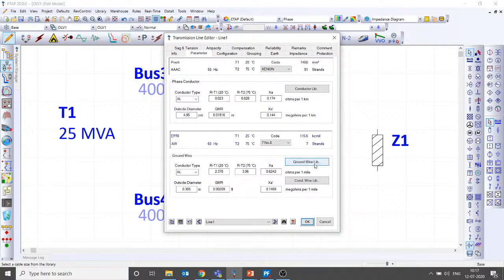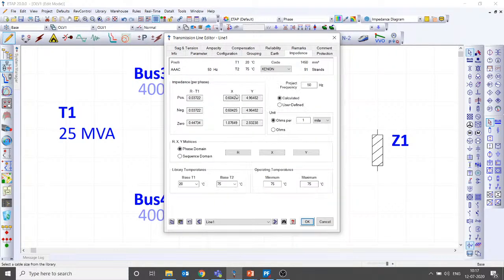If you get this reactance value into length 300 kilometers, sorry, that is per mile. That's the reason why it is appearing 0.6. That's right, sorry for that confusion. Yes, the x values will be approximately 0.4 ohm per kilometer. Previously it was in miles. That's the reason why it is showing about 0.67 or something. Now it is right. I mean 300 kilometer line reactance is 0.37 ohms per kilometer. So approximately 300 into 0.37, which you can put.